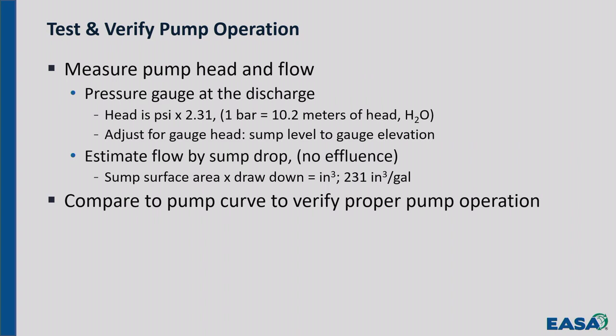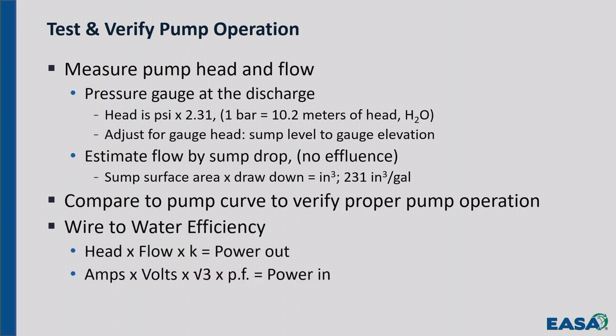Then you need to verify the head and flow if there are motor current problems. That gets back to the pump curve. That's just a little bit of information. And measure something called wire-to-water efficiency. The wire is the volts and amps and three-phase and the power factor of the motor. That's your power in. Your power out is head times flow divided by 3960. You don't need the efficiency because that's what we're measuring. Power out divided by power in is efficiency. How much water am I getting out for the electricity that I put in? That's a good number to have. You should know that number. Your customer should know that number and what it should be. So you document that.